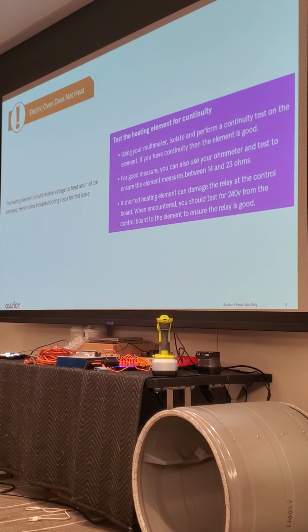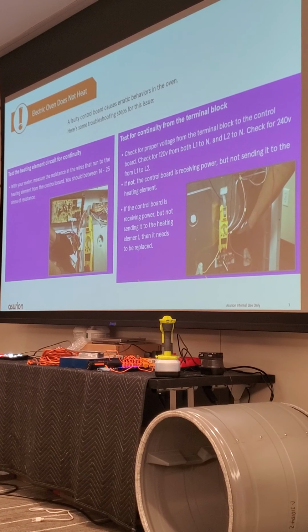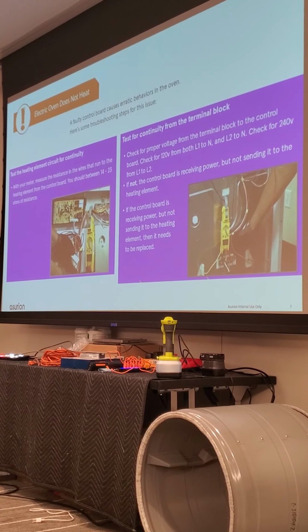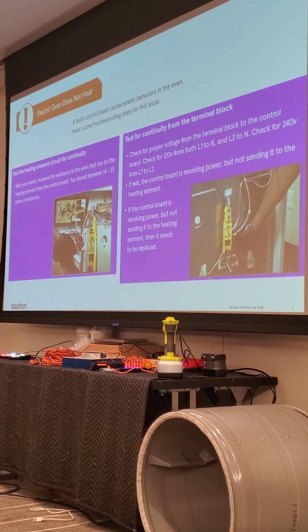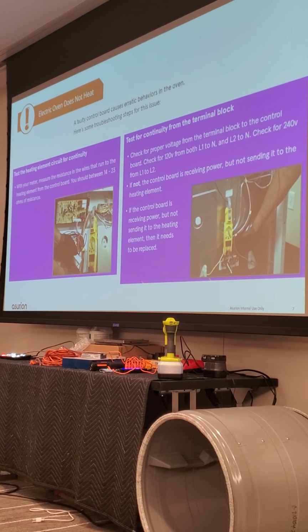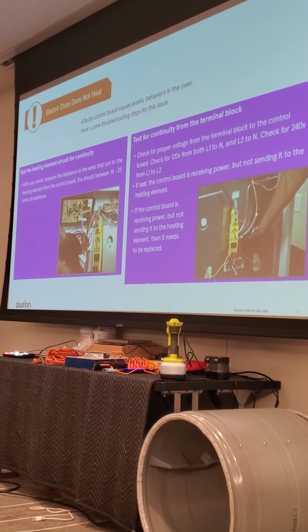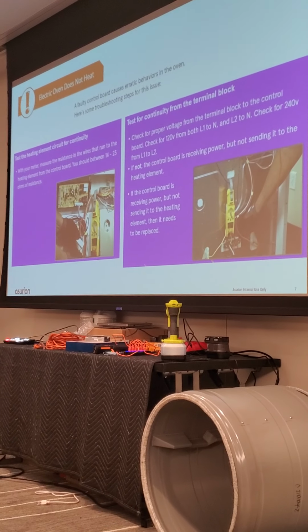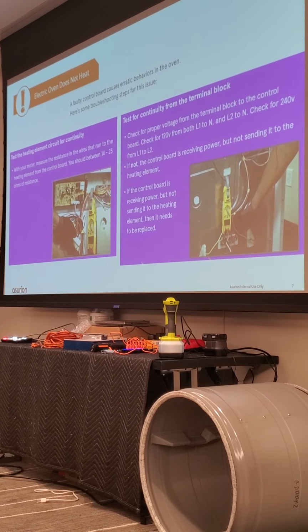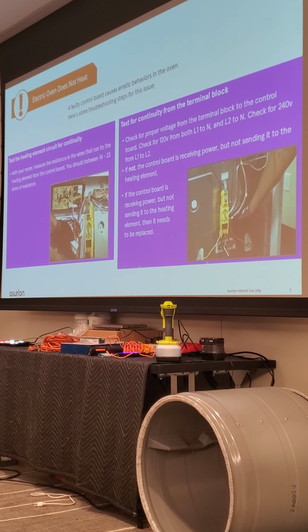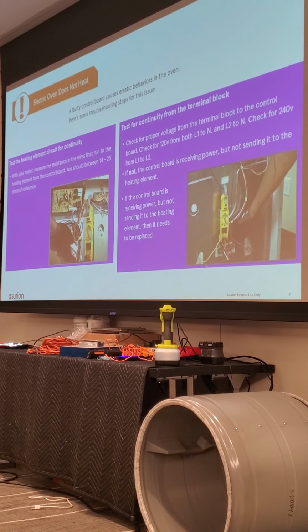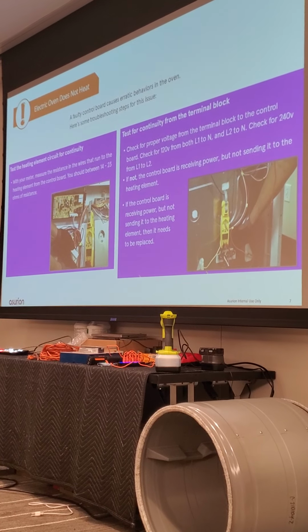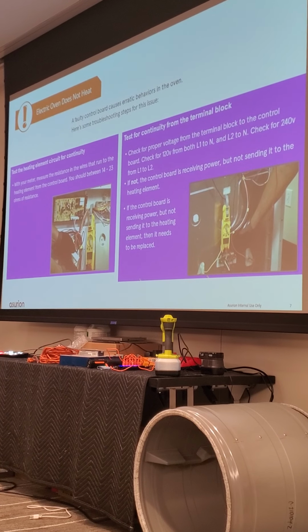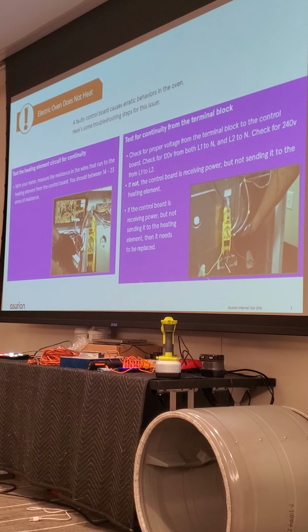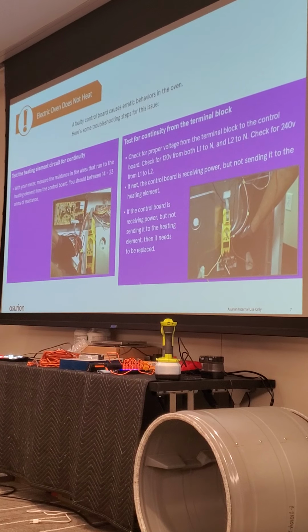Let's go back a few. Like it says right here, 14 to 23 - that may be your upper broil one, while your oven one may be larger, because broil may be a lot smaller element. And again, 240 volts from L1 and L2, but you need to know how the power goes through your circuit board and through your relays to get you that voltage. So that's just a few little troubleshooting deals.